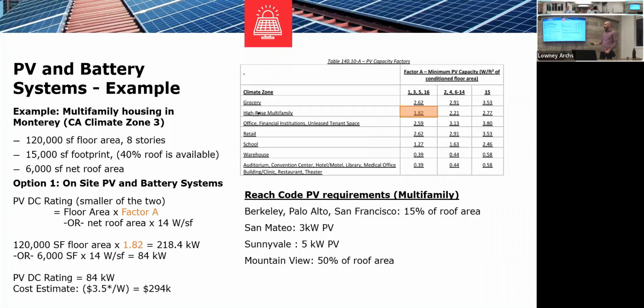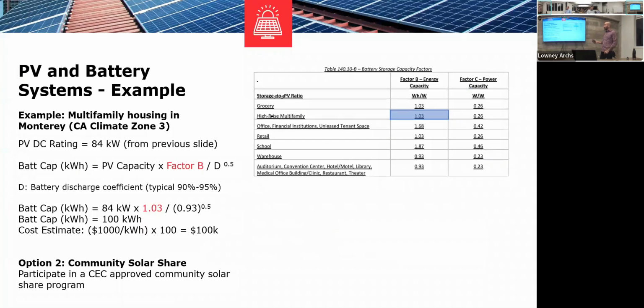After we calculate the PV capacity, which is 84 kW, we move on to calculation of the battery system for the building. We take the 84 kW PV capacity and multiply by the appropriate factor, which is 1.03 for high-rise multifamily. The 0.93 you see there is a typical battery discharge coefficient, a technical performance spec for batteries. You don't have to worry too much about that. Overall, this results in 100 kWh battery capacity. And the cost, again, ranges anywhere between $1,000 to $1,500 per kWh of batteries.